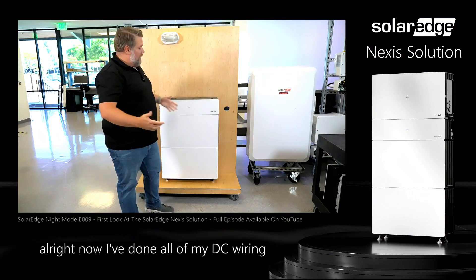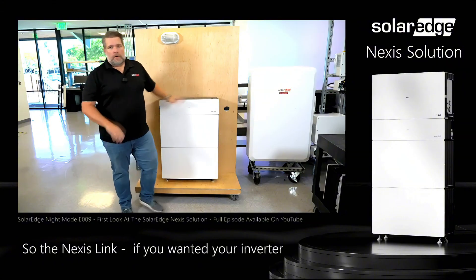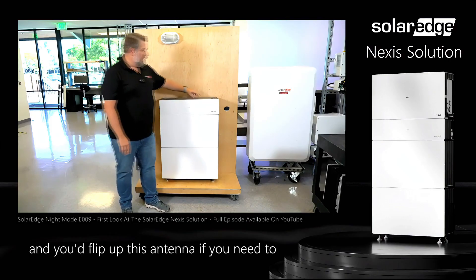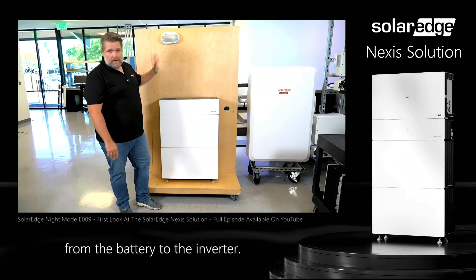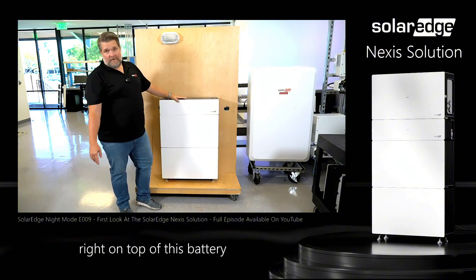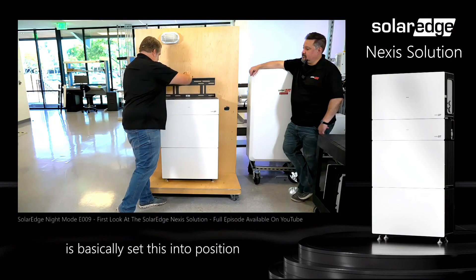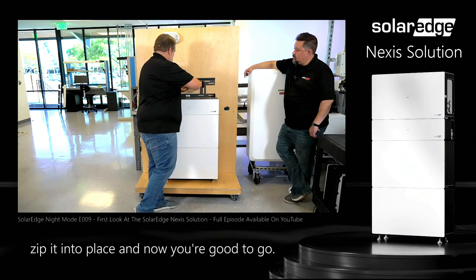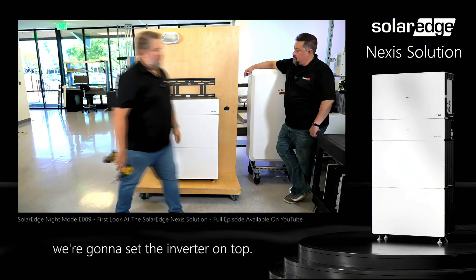I've done all of my DC wiring and created a battery. With the Nexis Link, if you wanted your inverter installed in a different location than where the battery is, you would stop right here, flip up this antenna if needed, and run DC wires from the battery to the inverter. But we made it so you can stack the inverter right on top of this battery. I made two little notches on top of the link — all you have to do is set this into position, grab your level, zip it into place, and now you're good to go. The bracket is in position and we're going to set the inverter on top.